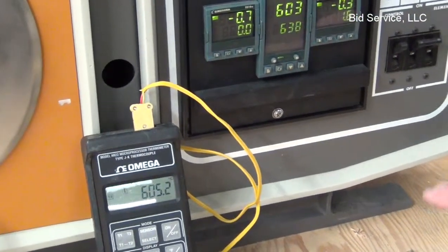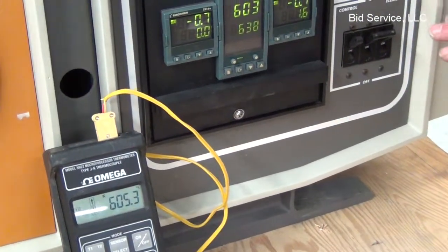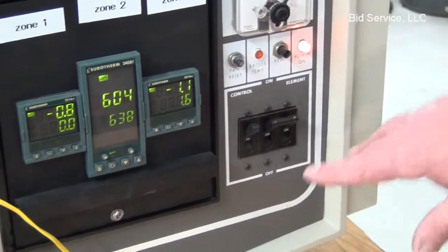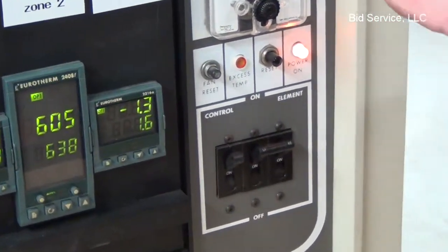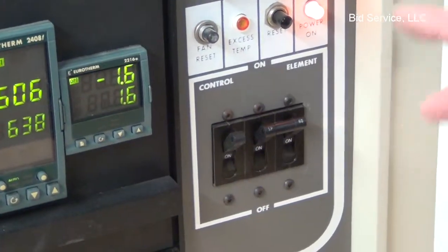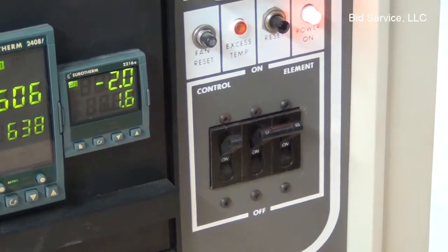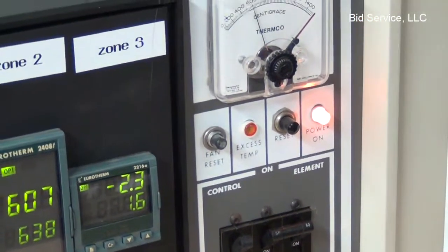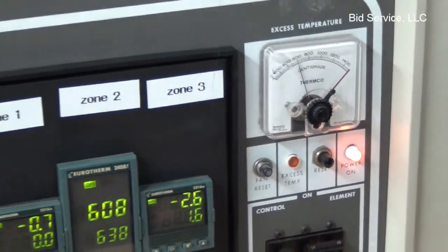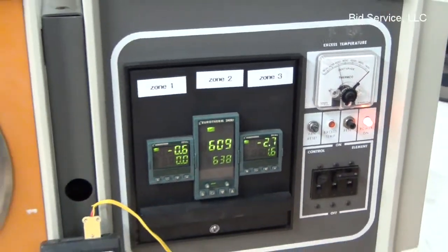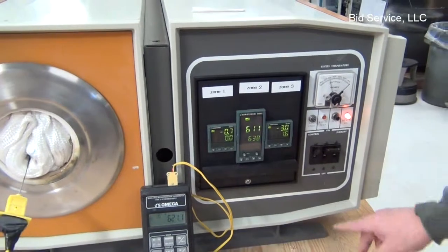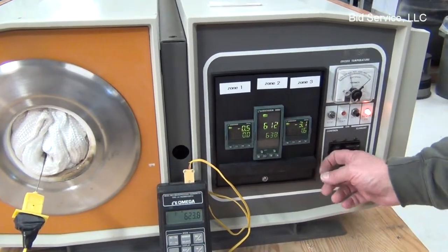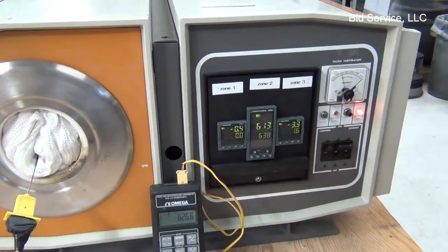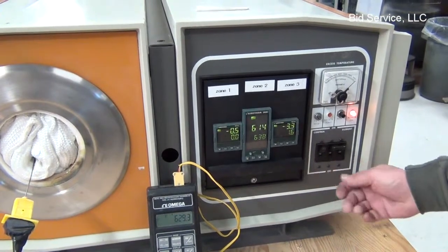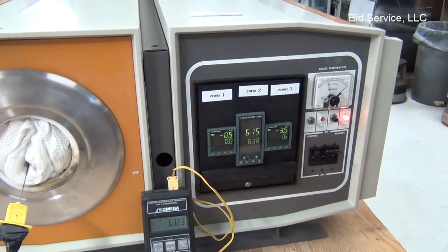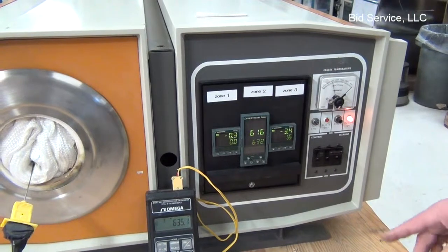While it's doing that, I want to point out over here you have your power controls. There is a main circuit breaker in the back. When that circuit breaker is turned on, the cooling fans that are internal inside here turn on so that there's always a cooling flow across the oven. And then you would turn on your control, which activates the control panel here. And then when you're ready to heat, you would flip this breaker up and it'll send the heating current.